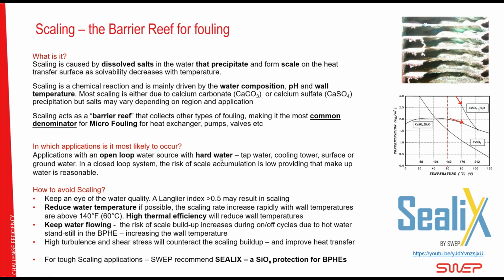Where do we see scaling the most? Well, hard water is the biggest driver, as I mentioned before, water composition. So if you have an open loop water source where there is new, fresh water all the time, that is hard. It could be hard tap water, could be again cooling tower, surface or groundwater. Then that's a high risk for scaling. In a closed loop system, again, if there is no infiltration, even if the starting water is kind of hard, the risk for scaling is not so big, since there will be a finite amount of salt to precipitate, and then it will not be so much anymore. But then, of course, if the makeup water is very hard and there will be more and more makeup water over time, this will also build up scaling. But it's mostly an open loop issue, scaling.